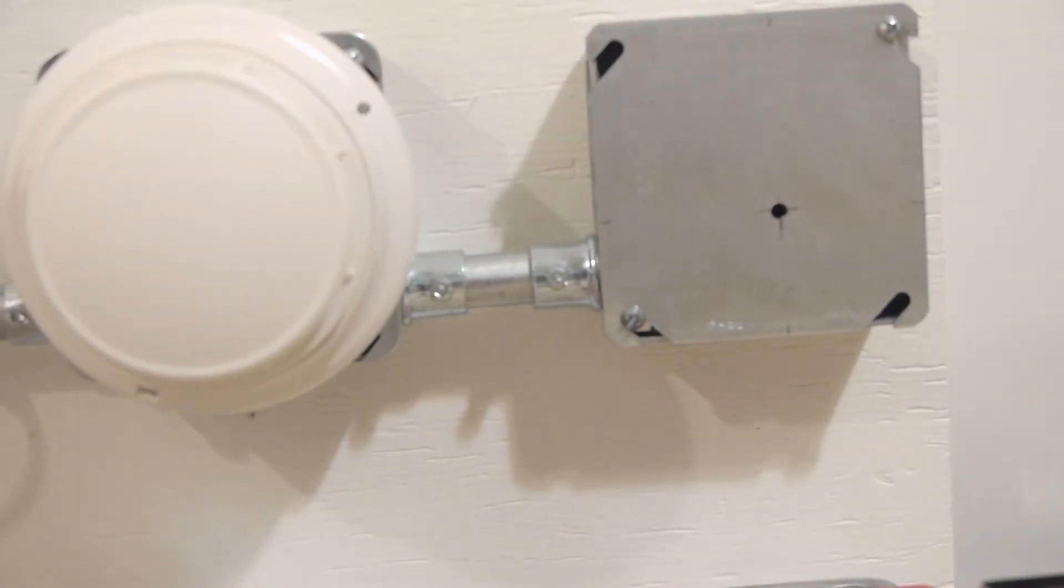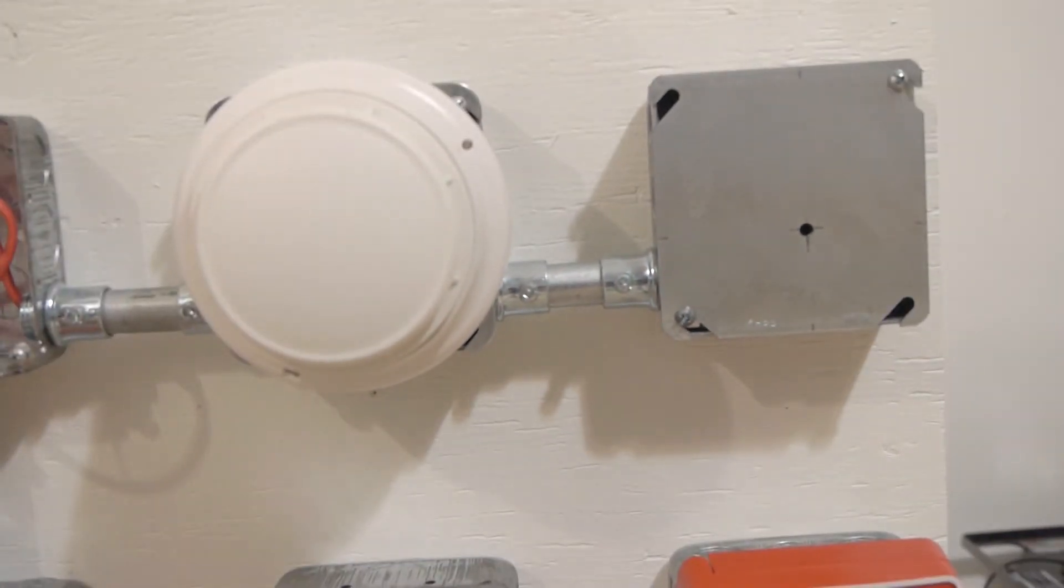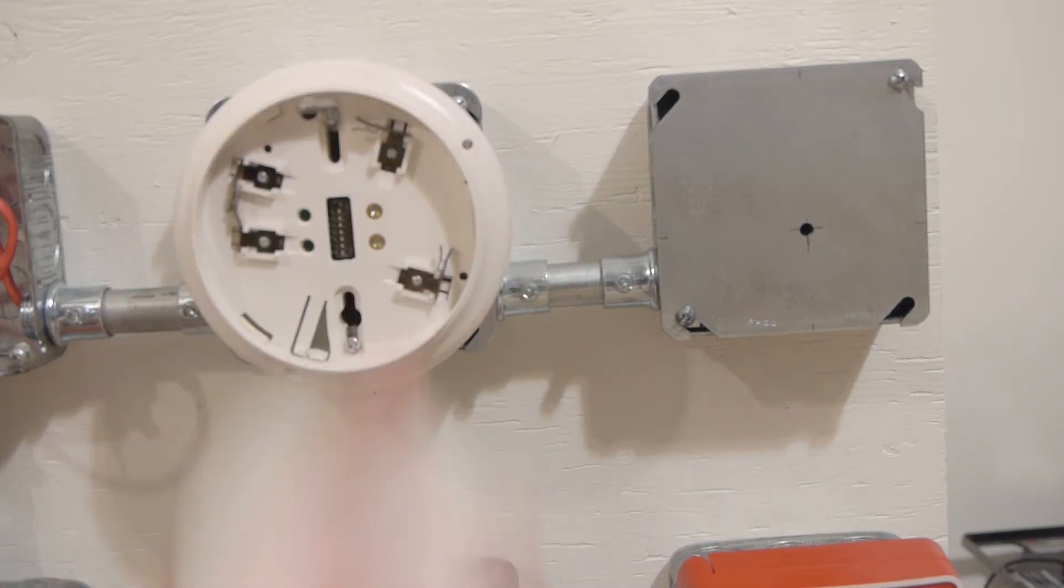Now lucky for me there's only two devices. There's a monitor module right here and there's a smoke right here. So I'm going to open up the smoke head and see if there's a ground fault behind there, which is commonly a chafed wire, water damage, or a damaged device.